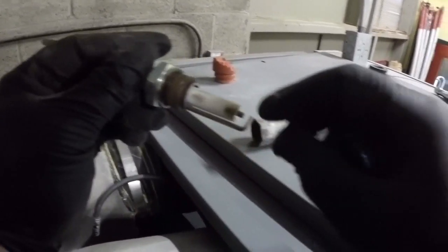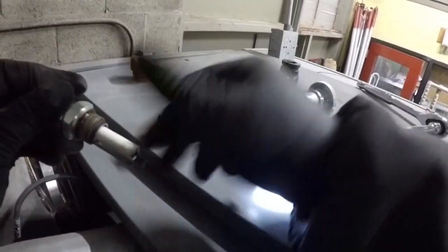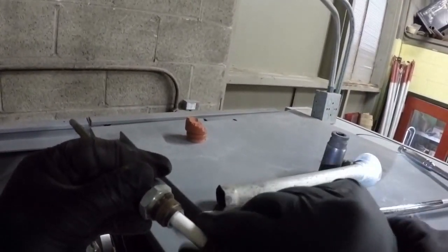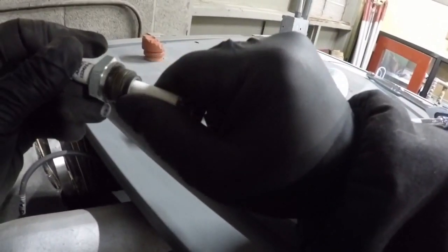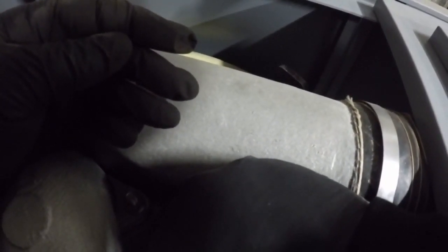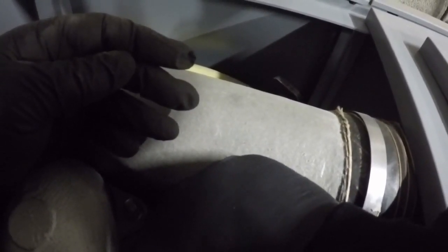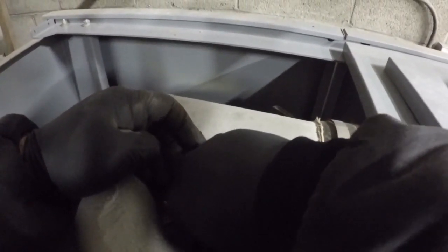We're going to once again check our porcelain out, make sure we don't have any cracks or breaks — anything compromising it. We're going to clean that up and then reassemble. All cleaned up. I won't be using any thread dressing of any kind — if you needed something you could use dielectric, but we don't want to impede our circuit to ground. We want to make sure that everything attached to our post is nice and secure because that is part of our circuit.